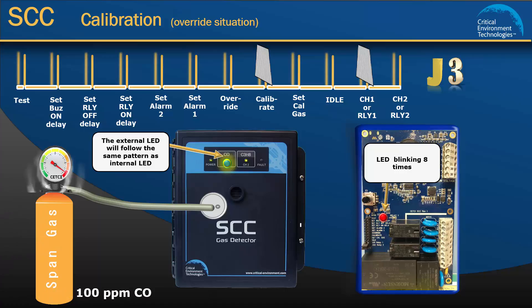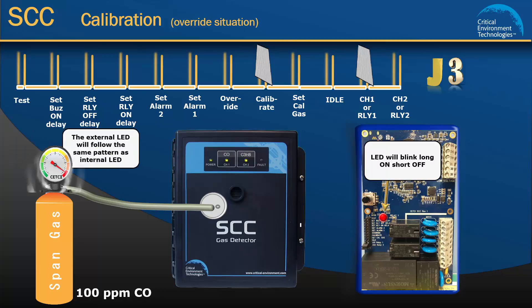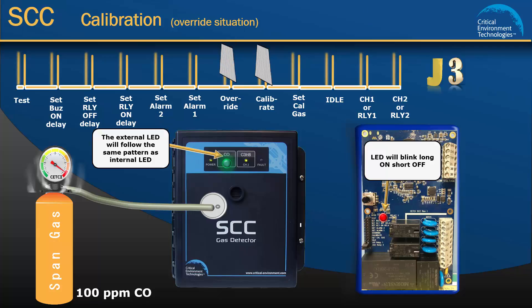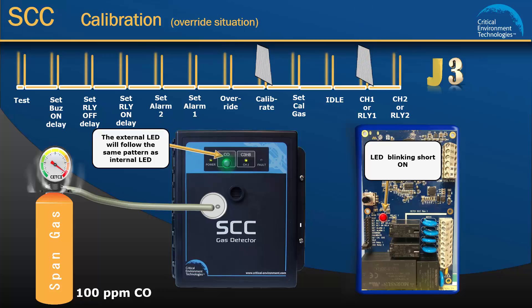Similarly, if during the span gas calibration the internal LED and external channel 1 LED lights blink a pattern of long on and short off, you will need to do an override. Leave the jumper on calibrate and move the other jumper from channel 1 to override. If outside the override range, the fault LED will turn on solid, the channel 1 LED will turn off, and the test points will output 4 volts indicating the sensor cannot be calibrated. If the override procedure is complete, the internal LED and channel 1 LED lights will blink short on. Return the jumper from override to channel 1 and the jumper on calibrate to idle. This completes a successful calibration of channel 1.